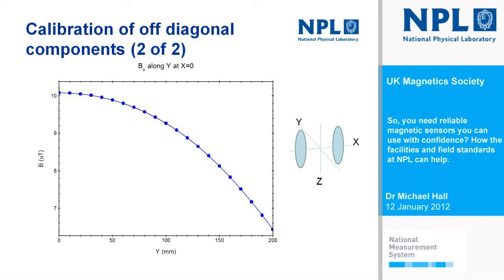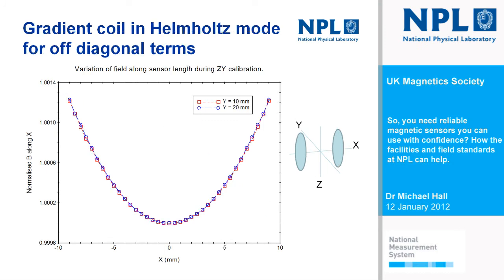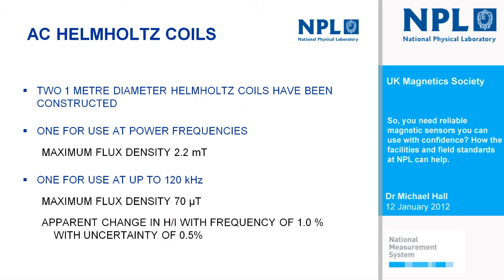Right, I want to move on now to AC field generation, still done in a low magnetic field lab because we have a nice clean AC magnetic field environment. The mains circuits are non-inductively set up, so that AC fields at 50 Hz are very small and sources of other AC fields are pretty much non-existent in that location. So we have two Helmholtz coil systems. We have one which is capable of 2.2 milli-Tesla at 50 Hz, and we have a coil system that is capable of 70 microtesla, only 70 microtesla at 120 kHz, but that is high enough.